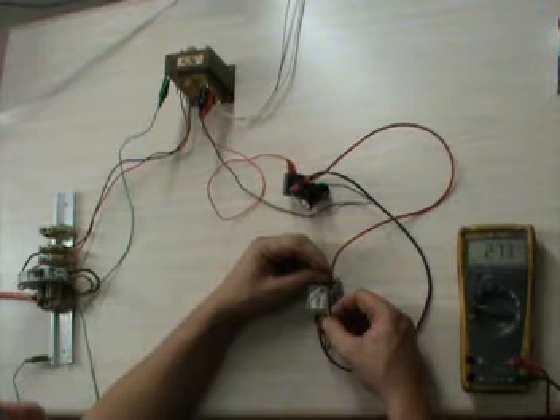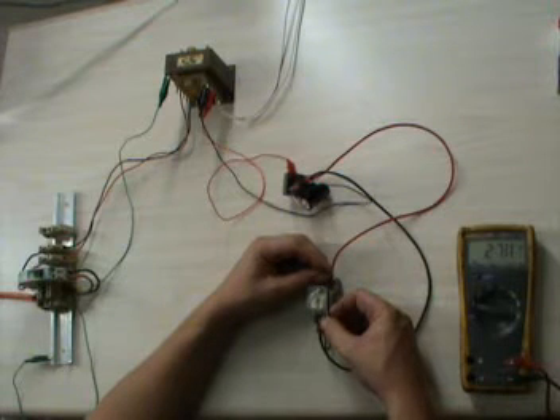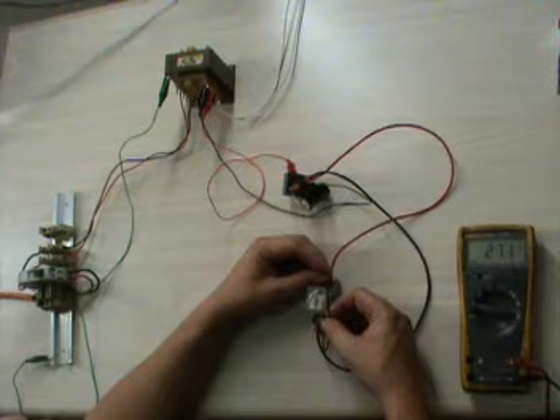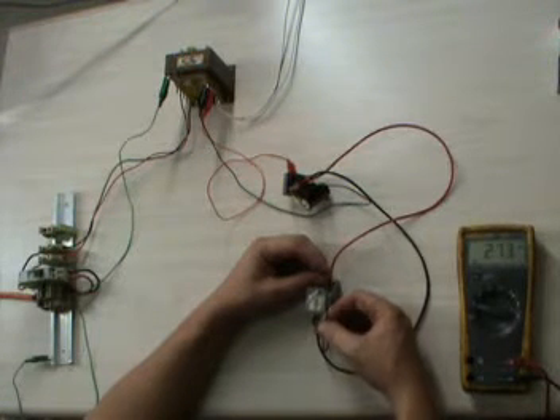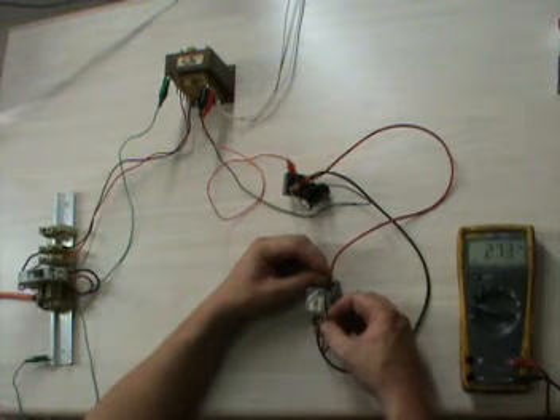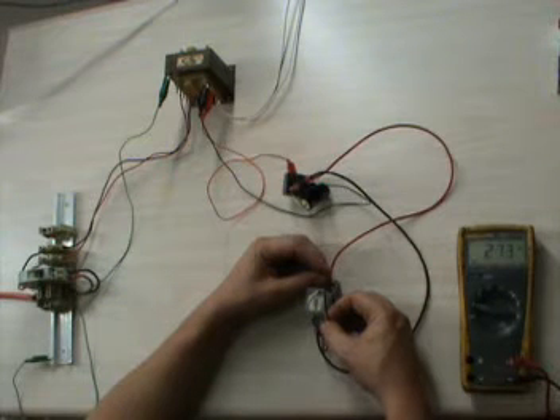At the moment, with this black jump wire, I'm effectively jumping out the latching and unlatching of the tickler relay, so this relay is energized. If I let it off, it'll go back into oscillating; put it back on and the relay's on. Pretty straightforward.